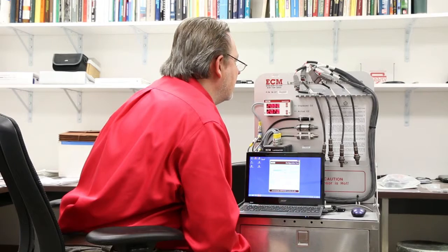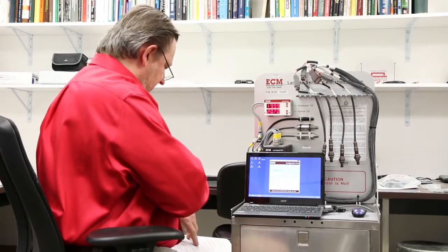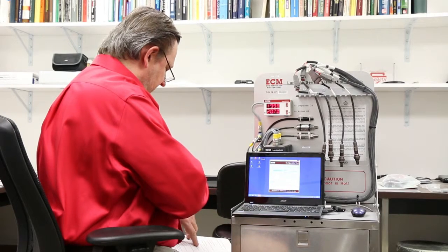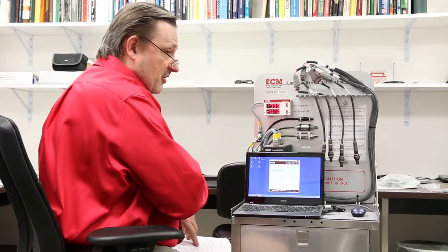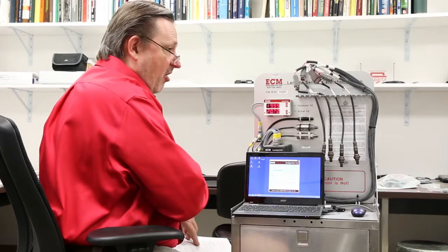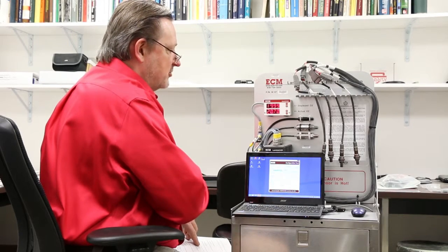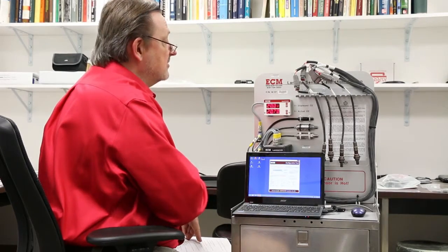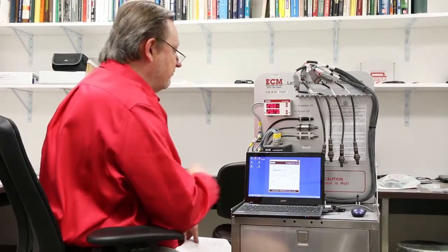And I haven't quite waited a minute. Let's give another 15 seconds here. Now the sensors aren't ready to calibrate, but they are on, and the electronics and the Lambda CAN modules have a chance to see if the sensor is okay. There's no use calibrating a sensor that's failed. So, here we got our 15.